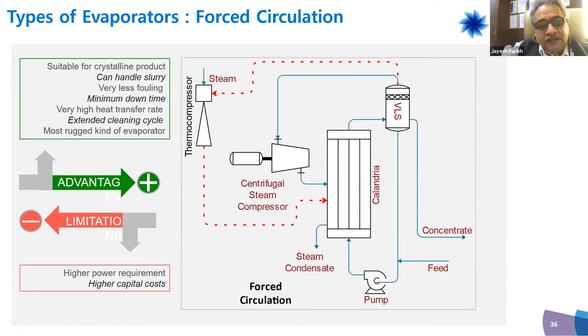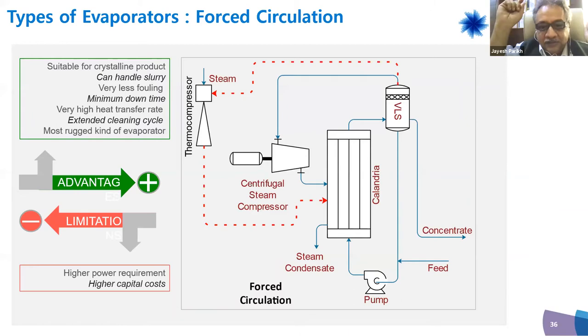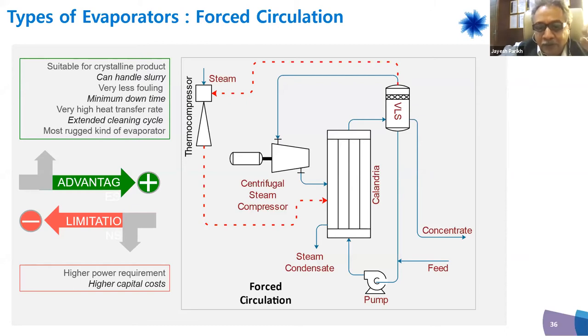Once falling film reaches a controllable TDS and non-scaling tendency, the process transfers to forced circulation. A multi-effect evaporator (MEE) may combine falling film for early effects and forced circulation for later harder stages — two, four, five, or six effects. In forced circulation, tube velocity must be maintained carefully; too high a velocity increases power consumption. Optimization balances velocity, heat transfer area, carryover tendency, and foaming tendency. The design objective is to reduce CAPEX and optimize the MEE configuration.